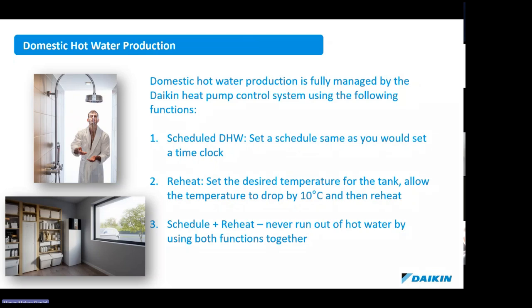And then it's already pre-programmed for what we call Legionella protection or disinfection. Generally in Daikin, it's pre-programmed for a Friday night to go to 60 degrees for an hour. But you can change that if you want, say your schedule changes to Tuesday morning or whatever. That's no problem. So you have full disinfection already managed in the system. Yeah, you can set schedules if you want to.